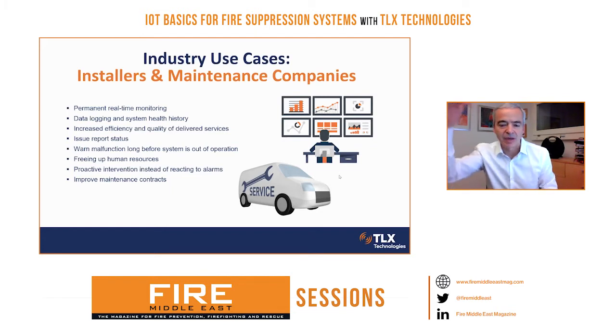At the same time, if there were a vertical acceleration in that accelerometer, those forces would indicate there was a manual activation of the system. In the same case, a solenoid would have voltage and current if it was actuated by the panel. And if it wasn't actuated by the panel, there wouldn't be a data log showing voltage and current. So the amount of information that can be gathered on that type of event is huge and so valuable.